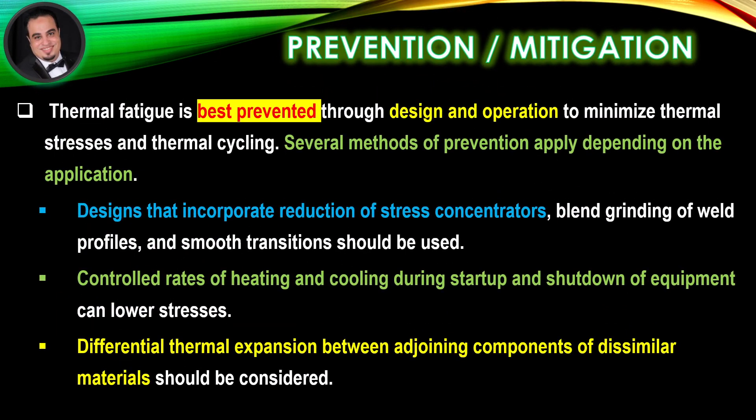Prevention and mitigation: thermal fatigue is best prevented through design and operation to minimize thermal stresses and thermal cycling. Several methods of prevention apply depending on the application. Designs that incorporate reduction of stress concentrators, blend grinding of weld profiles, and smooth transitions should be used. Controlled rates of heating and cooling during startup and shutdown of equipment can lower stresses.